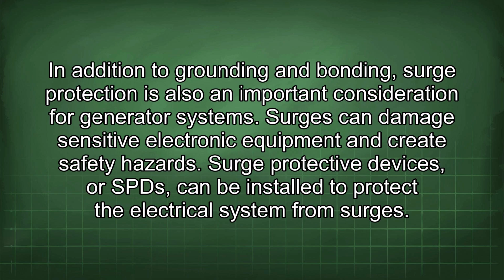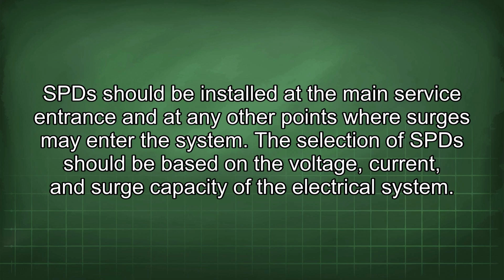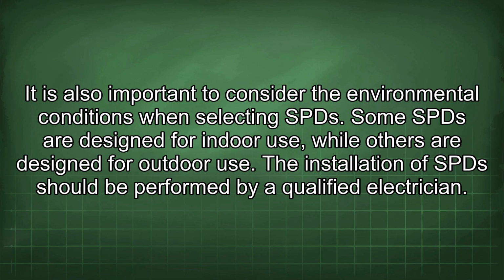In addition to grounding and bonding, surge protection is also an important consideration for generator systems. Surges can damage sensitive electronic equipment and create safety hazards. Surge protective devices, or SPDs, can be installed to protect the electrical system from surges. SPDs should be installed at the main service entrance and at any other points where surges may enter the system. The selection of SPDs should be based on the voltage, current, and surge capacity of the electrical system. It is also important to consider the environmental conditions when selecting SPDs.